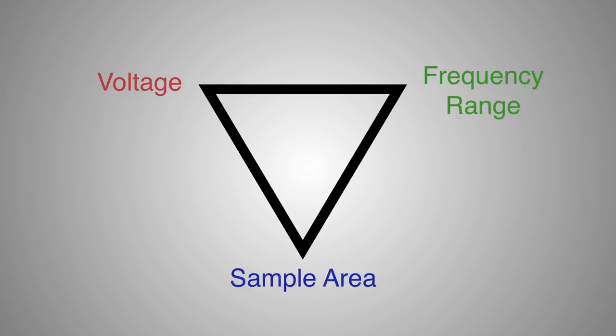Radiant defines its tester ranges by 3 parameters: voltage, frequency, and sample area. The sphere formed by these 3 parameters is the envelope within which the associated Radiant tester will maintain 0.5% accuracy of any measurement for a single pass with no filtering of the data.